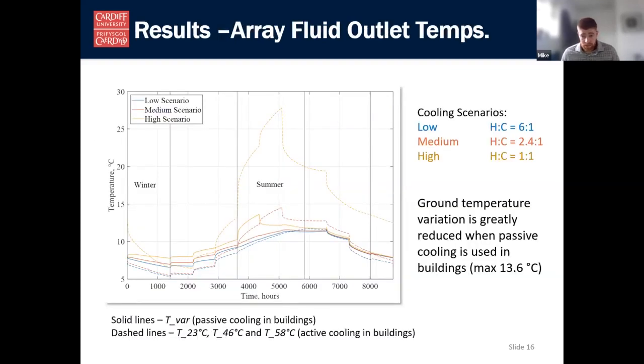In this slide, we see early results as the solid lines, and those solid lines are for the T-var configuration with passive cooling, and the dashed lines are for the other configurations where active cooling was required. And this demonstrates the effect of active cooling on ground array temperatures, since more heat must be rejected to the ground than when rejecting heat at elevated temperatures. So there's a feedback loop here which we wouldn't have captured without running these 2 simulations side by side.